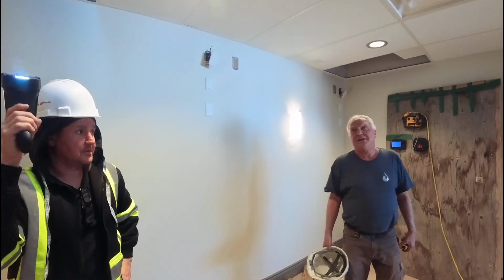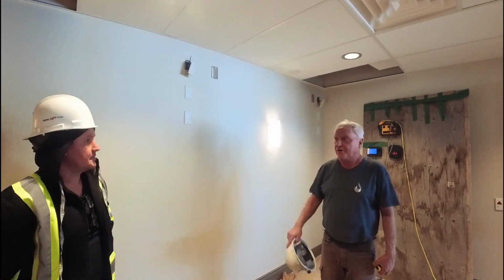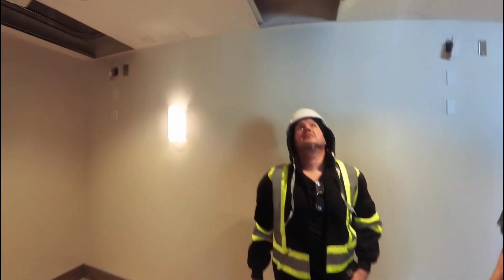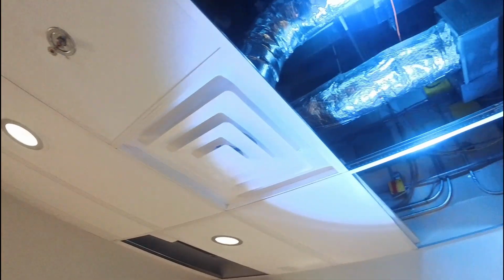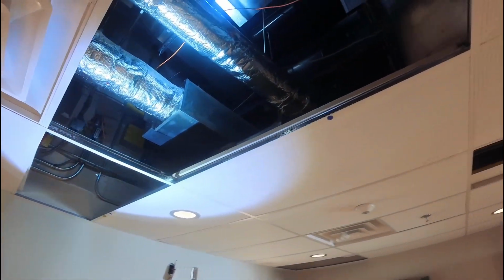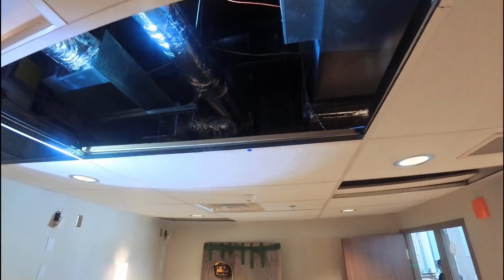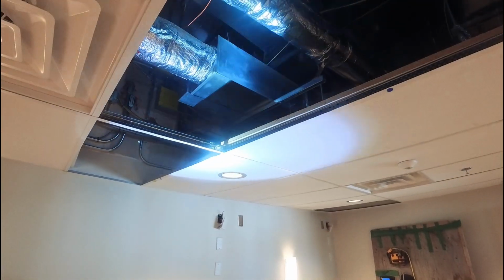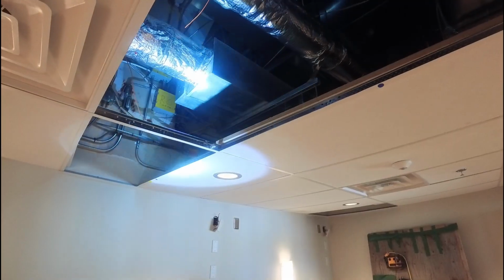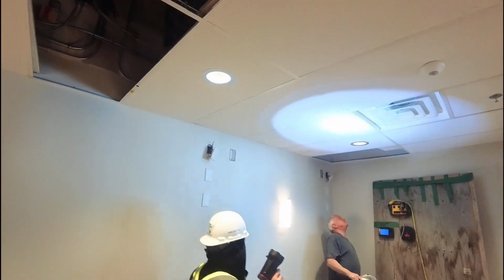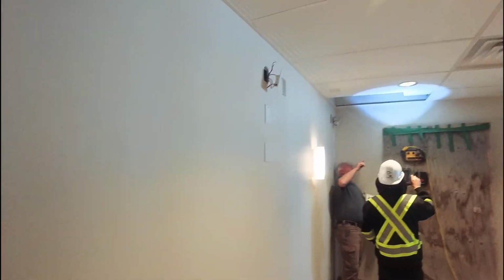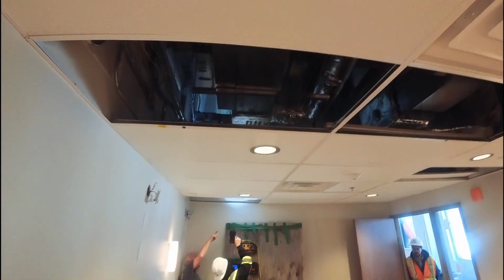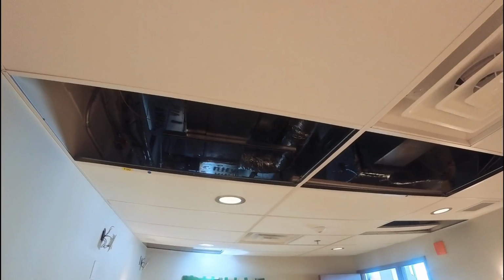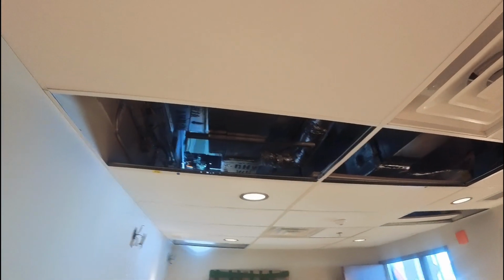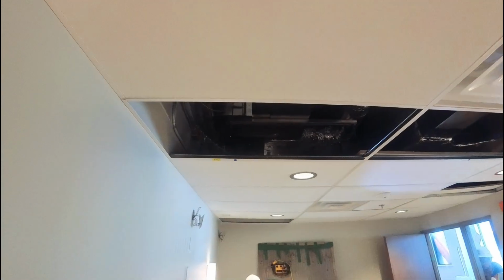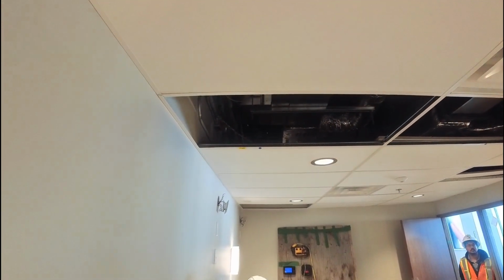Okay. And let's say there was nothing coming out of that supply diffuser. Let's see what we'd think about with that. We'd say, I wonder why that supply diffuser has a problem. And we'd go and follow the ductwork that it's coming off of and keep following it. It comes off the VAV back here. You can see the round duct coming off the end of it. You can see it from here, or you can see one right there as well. We're all the same here, right?